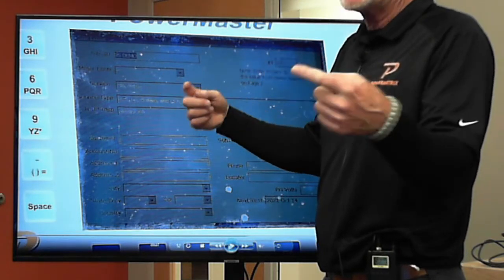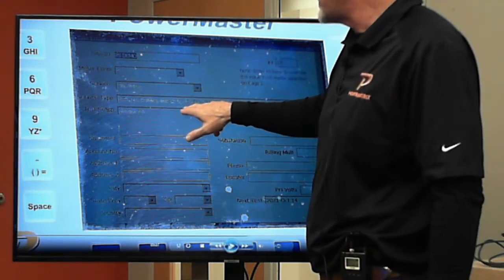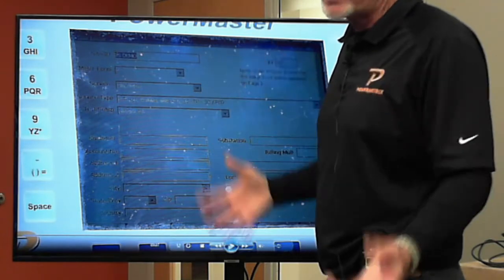So if they're only using 2 CTs instead of 3, and they've got 2 conductors running through the same CT, you've got to look at that stuff and decide, is it 3 voltages and 3 currents or not? That way you will have the correct service type with that site, and then it'll test correctly.